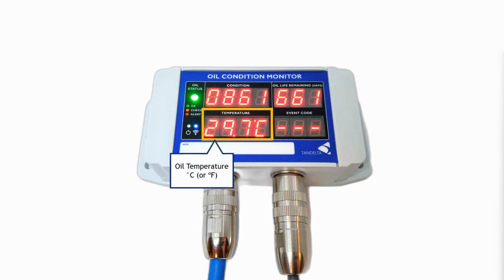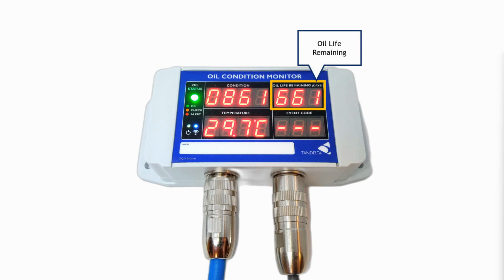Below TDN, you have the oil temperature, which is displayed in your preferred scale of either degrees Celsius or degrees Fahrenheit. The top right-hand box displays the days to the next service. This tells you how many days you have before you'll need to change the oil, based on the rate at which the oil condition is changing.